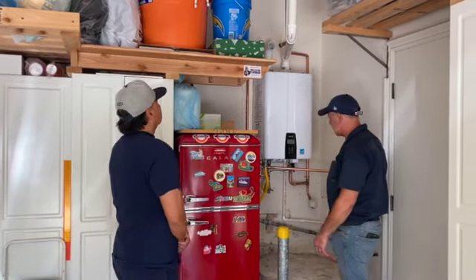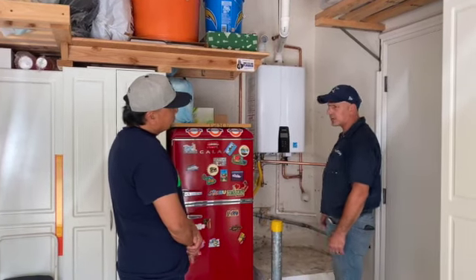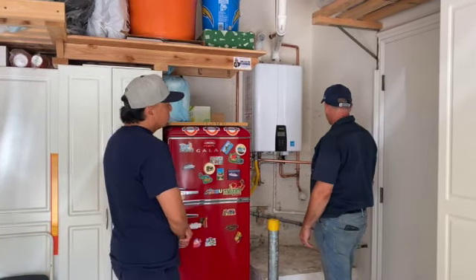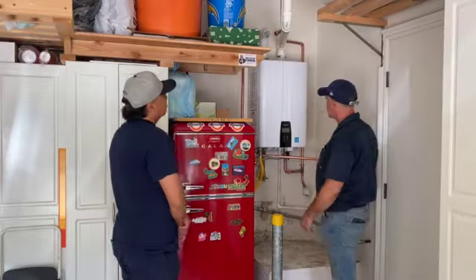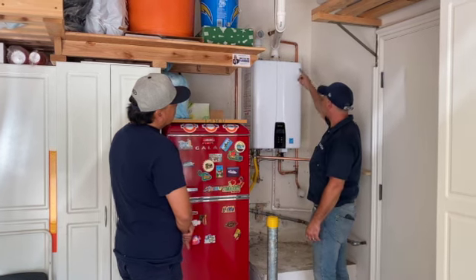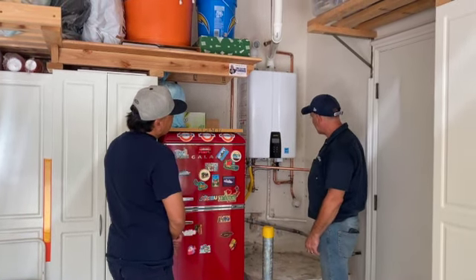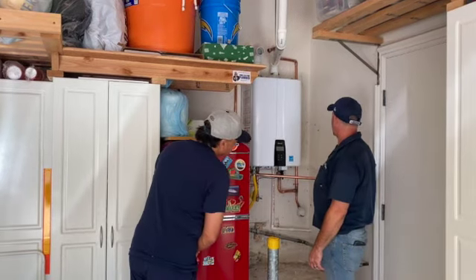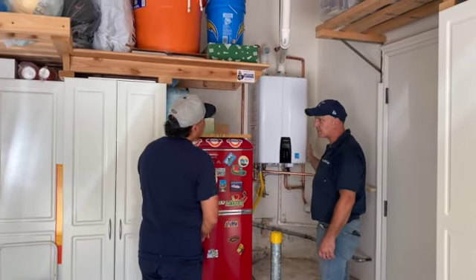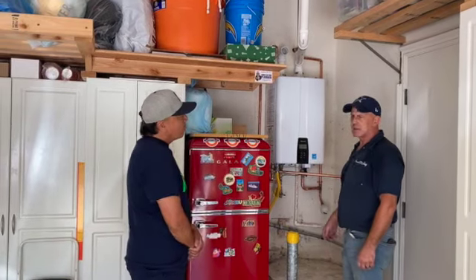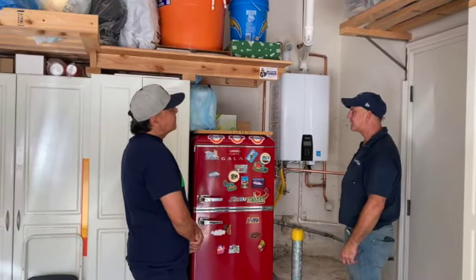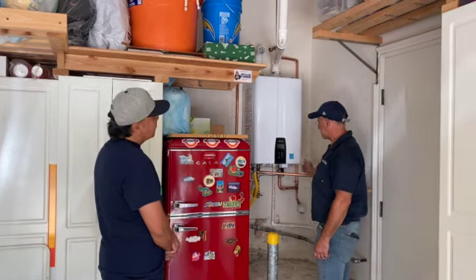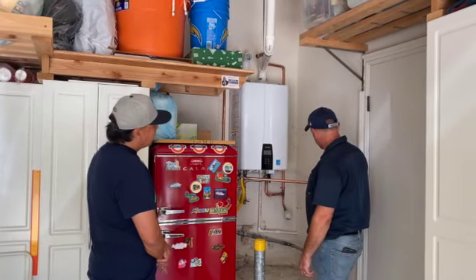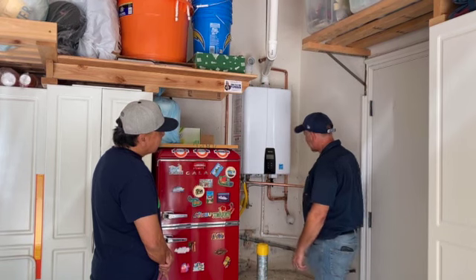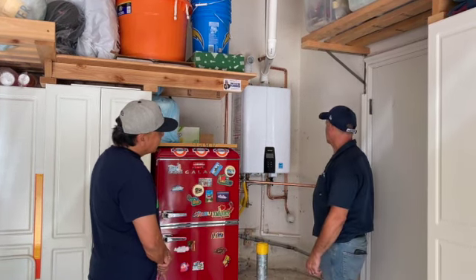You can see that in a retro application like this, you're kind of stuck putting your plumbing together based on how the old plumbing was. This one's a retro from a 75-gallon water heater, so we had to send the lines from up high down low. Unfortunately, Navien doesn't have the option in this condensing style unit for a top connection like they do in some of their non-condensing units. So here we just had to deal with what we had, like where the gas line was and where our pressure relief line was - not optimal, but we make it work.